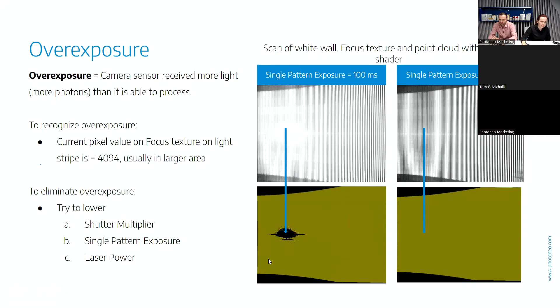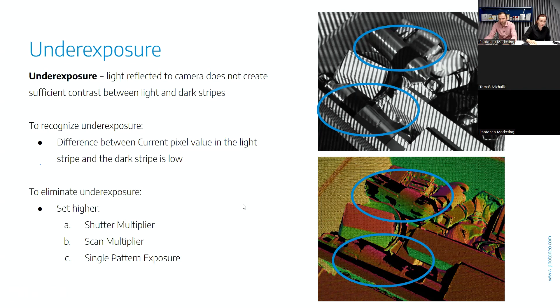Then we can have underexposure. Underexposure means that the light reflected to the camera does not create sufficient contrast between light and dark stripes. We can see in these parts of the scan that the light and dark are bleeding into each other, they are disappearing. Also the reconstruction in these parts of the point cloud was not successful. If you are dealing with underexposure, it means that the light is not sufficiently reflected back to the camera, and you might want to set a higher shutter multiplier or single pattern exposure, prolong the scan, multiply the amount of photons sent out by the device, and as a result, have a better 3D point cloud.